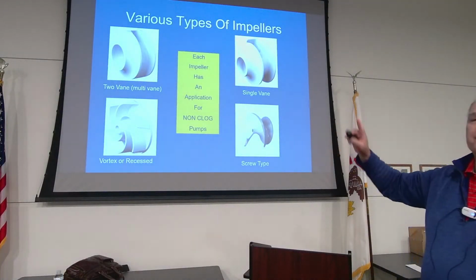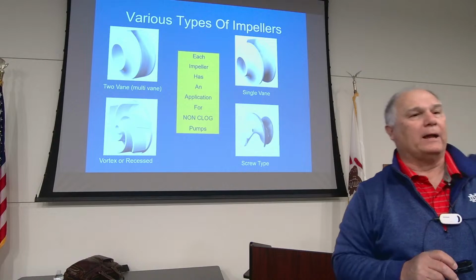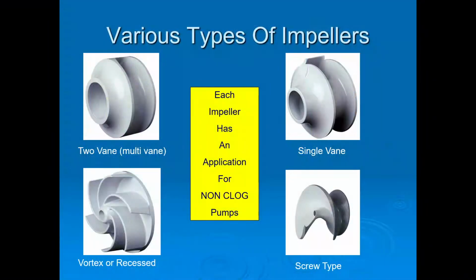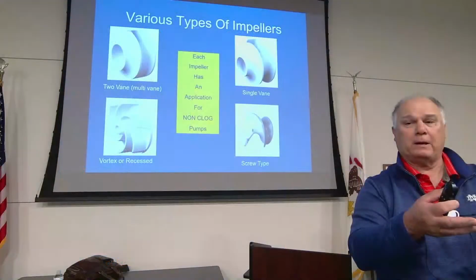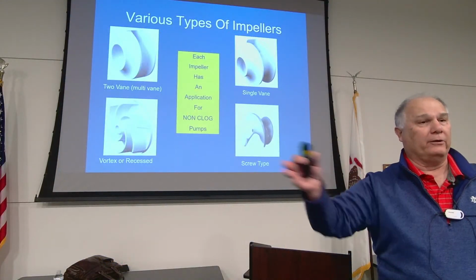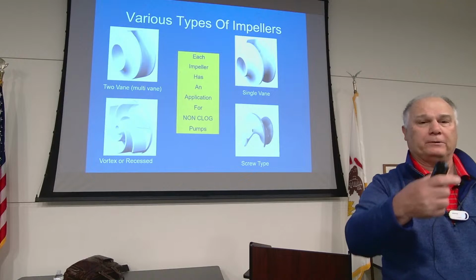So there are 4 impellers that are available. Now that we're down from the motor, through the seals, through all that kind of stuff, let's get to the impeller discussion. We have the 2-vane impeller, which is the multi-vane. Some manufacturers do 2-vane, 3-vane on really big pumps. One of our competitors does a 5-vane impeller pump. Probably not the choice that I would make, because when rags come up, instead of 180 degrees, that rag could go from one side to the other.